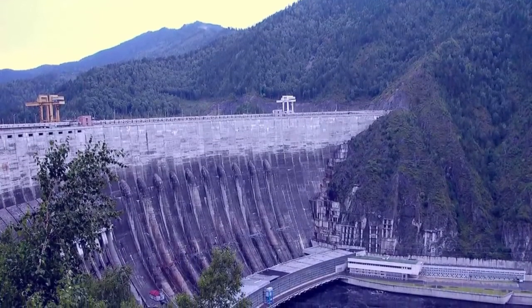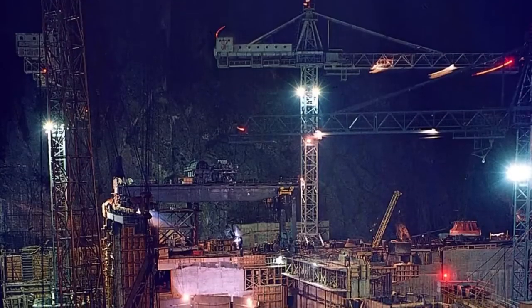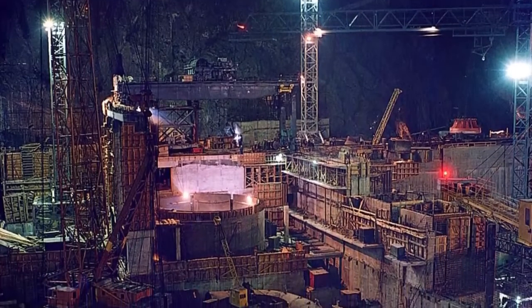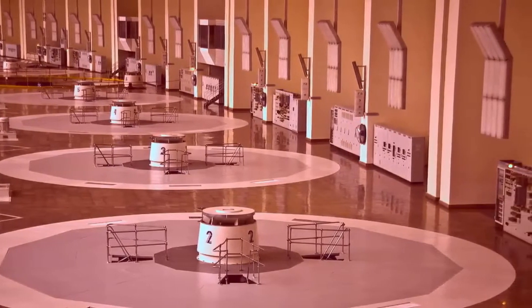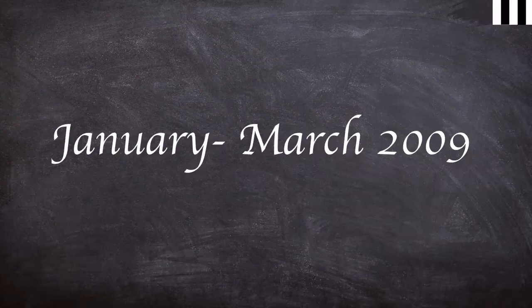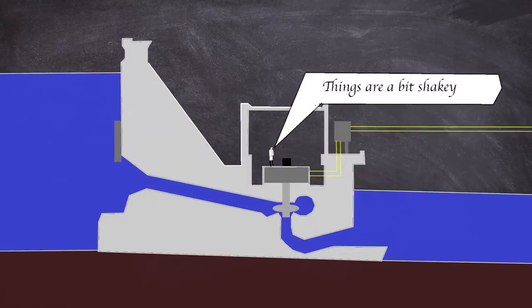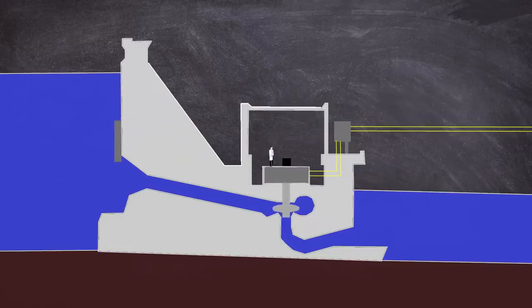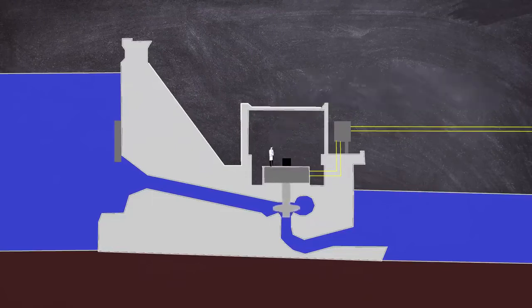The hydroelectric plant's lifetime had been mired with various issues. Many of the turbines experienced seal, vibration, and bearing issues, as well as several floods. Turbine 2 had its fair share of issues ever since its installation in 1979, having taken the brunt of extreme forces during its operating life. By the early 2000s it was showing its age with cracks in the turbine runner and bearing issues. Between January and March 2009 the plant was undergoing modernization, including a new automatic control system to match output power demands. Once again turbine 2 had defects along its blades, and once the work was completed the runner had not been rebalanced, leading to vibrations once again. Although deemed within design specs, this vibration would wear down the bearings and mountings. Over the coming months the vibration began to exceed specifications and the turbine was shut down for investigation.